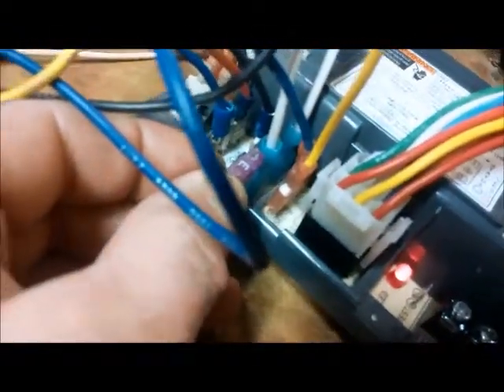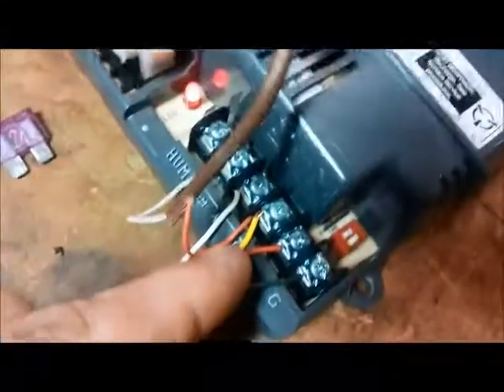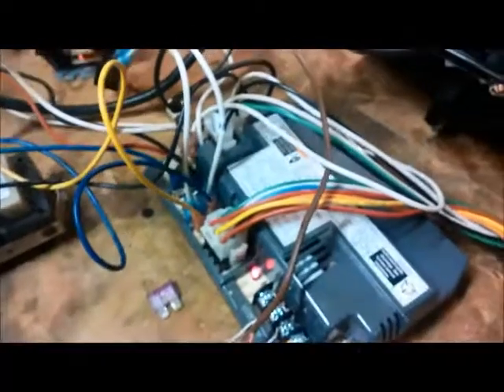And that would take out the fuse on the board, which should be mounted right in there. I've got a small breaker in place of the fuse right now just so we can demonstrate a short. So your transformer is fed into secondary 1 and secondary 2, fed up through the fuse before it heads to R over here.